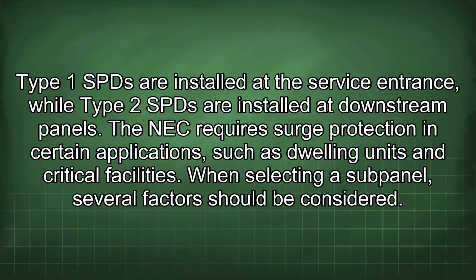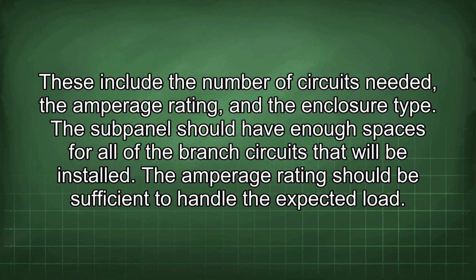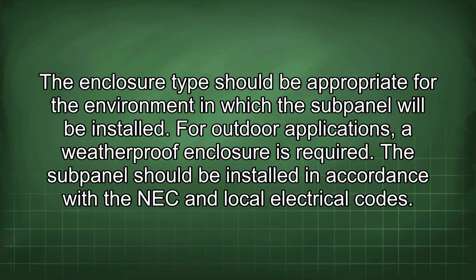When selecting a subpanel, several factors should be considered. These include the number of circuits needed, the amperage rating, and the enclosure type. The subpanel should have enough spaces for all of the branch circuits that will be installed. The amperage rating should be sufficient to handle the expected load. The enclosure type should be appropriate for the environment in which the subpanel will be installed. For outdoor applications, a weatherproof enclosure is required.